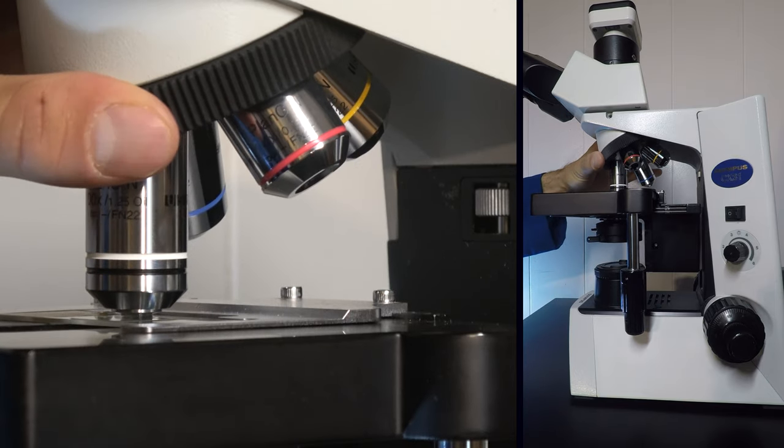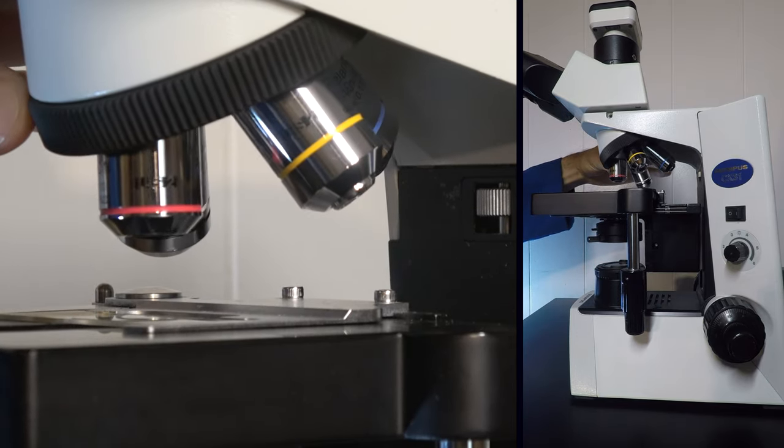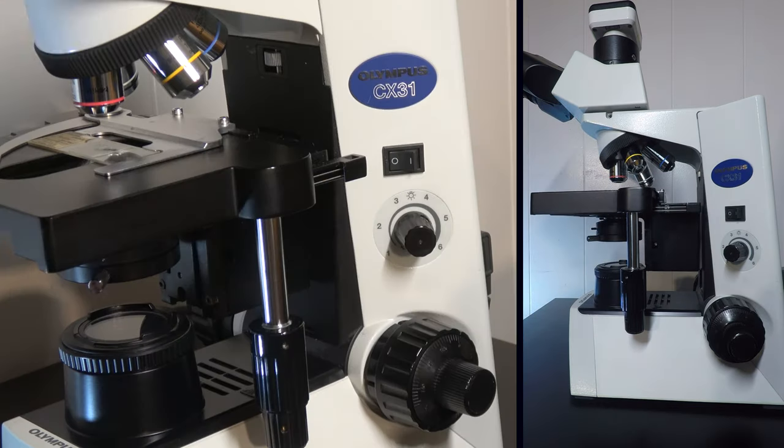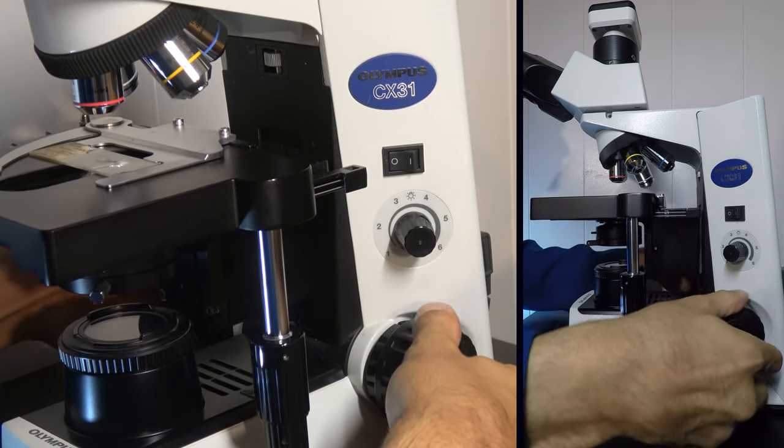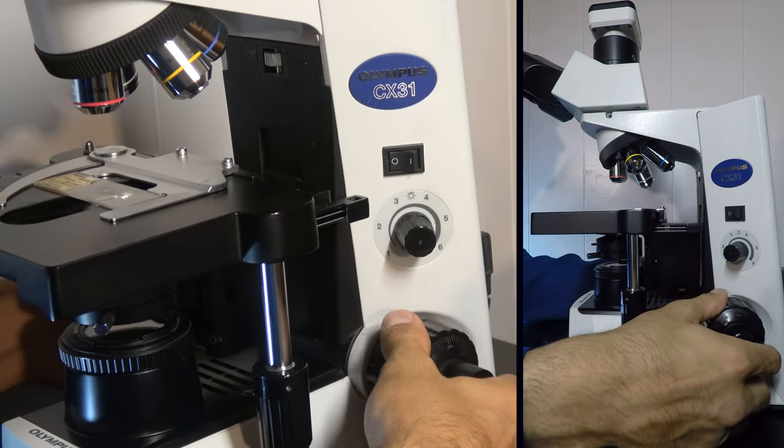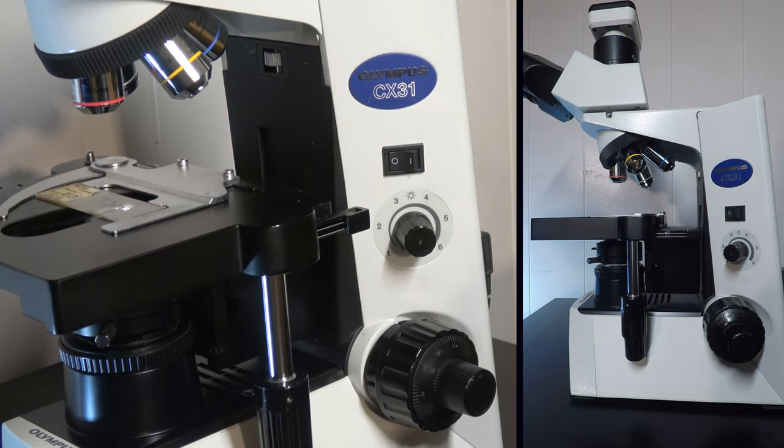If you are at the highest objective on your scope, it is safe to go directly to the lowest objective. This gives the most working distance again to allow for the stage to be moved without accidentally adjusting the stage up and crashing it into the objective lens.